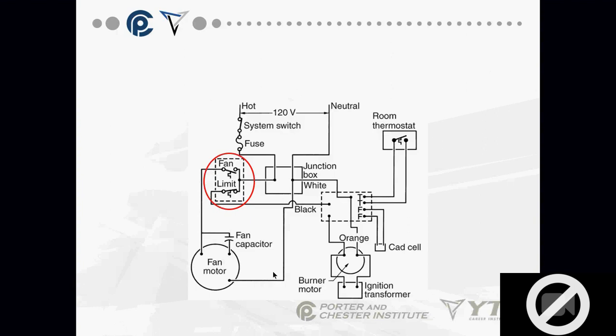Okay, when you look at this, this is a wiring diagram. This is not a ladder schematic. When you look at a wiring diagram, you'll be able to see where you bring your hot and neutral in. We'll bring my line into my fan limit switch. One side of it controls the fan motor. The other side of it goes to my primary control. My black, my white, and my orange. Okay. Where's my transformer for my thermostat? Where's my transformer?